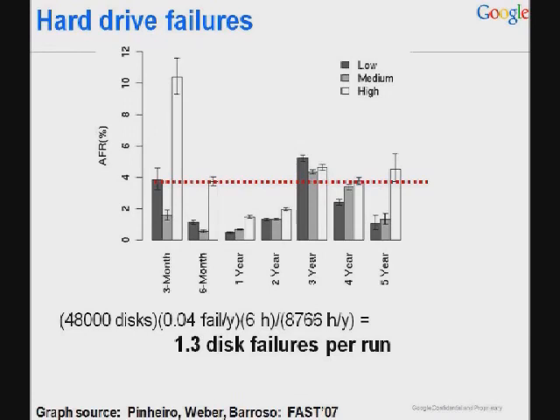The buckets, high, medium, low, are actually batch numbers. We have found that for the most part, disk failure rate is not correlated to vendor, OEM, or firmware, but is correlated to batch numbers. This has an important lesson for personal life: when you buy a large number of terabyte disks for your RAID 5, check they're not consecutive serial numbers, because most often they will be. As we've seen, failures are correlated across batch, and RAID 5 will not help when you lose 2 disks in the same batch at approximately the same time. Not that this has happened to me or anything.